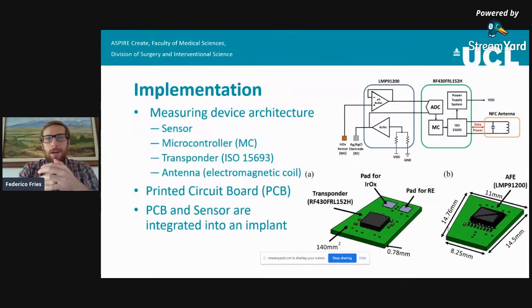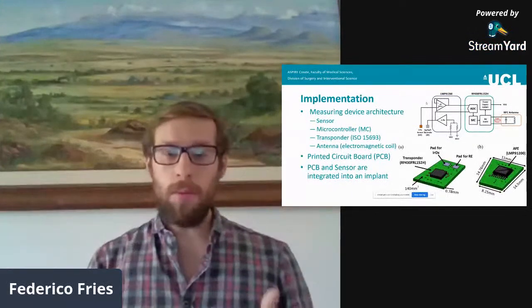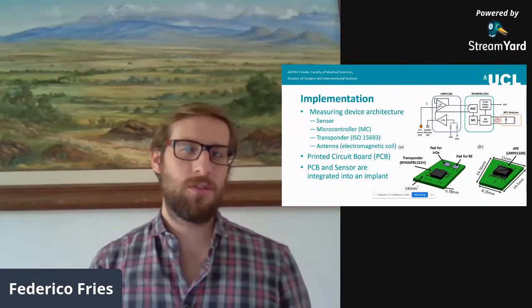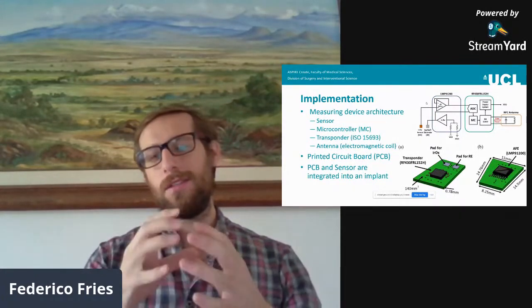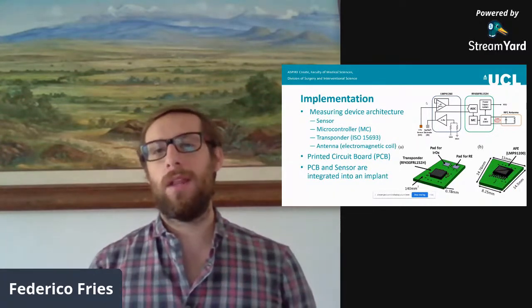Basically, the architecture of these implants has a sensor, which is the iridium oxide sensor. Then we have a microcontroller that processes the signal from the sensor and then transfers it into a transponder. Everything is actually encased in this integrated circuit, the blue one, the green one. And the only thing that the transponder does is translate the information into a protocol that is later sent through the antenna to the external device, which is the cell phone. In this case, this blue box is a circuit that helps minimize the error measured by the iridium oxide sensors. These are very sensitive sensors. There's a lot of noise in the body, you have to imagine. And this box helps you minimize this error and increase the accuracy of the device.